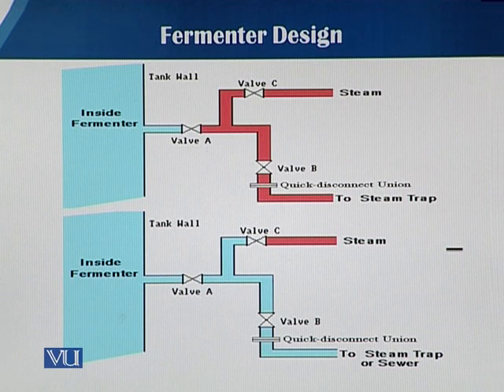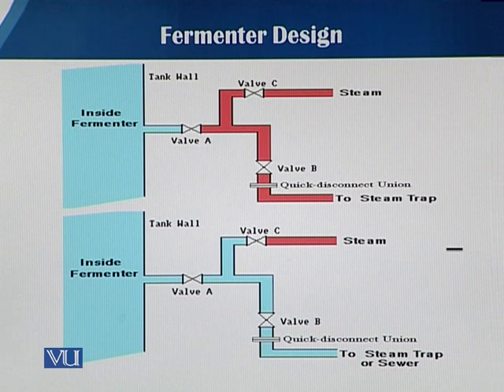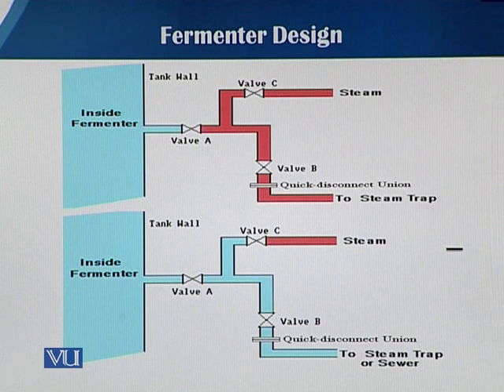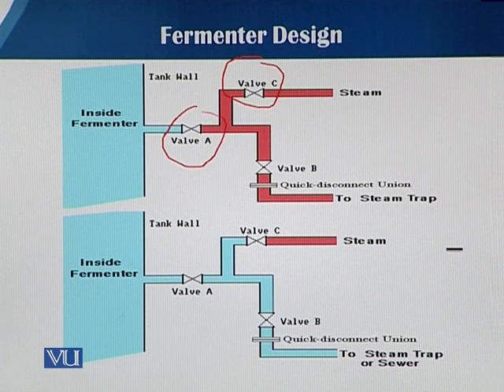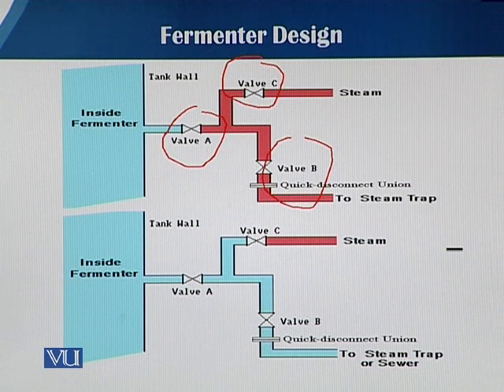In this slide you can see there are different lines. Concerning sterilization, in large-scale fermenters this is mostly carried out through steam, controlled by different automatic valves. The blue color shows the inside of the fermenter, and the red lines show the steam, with different valves — valve C, valve A, and valve B. If valve A is on, the steam can pass through into the inside of the fermenter, but that is only needed when we have to clean or sterilize the fermenter inside.